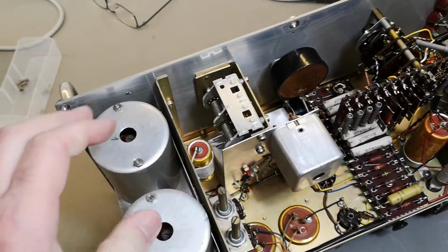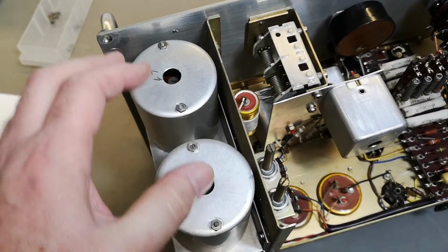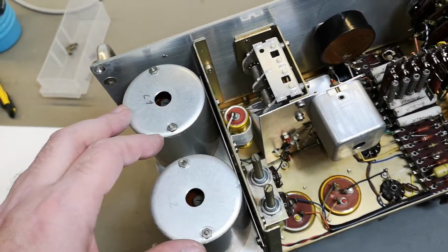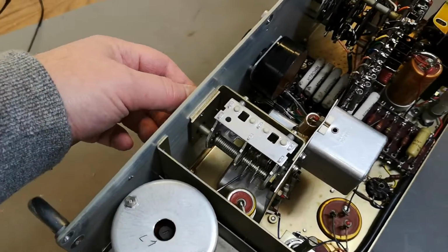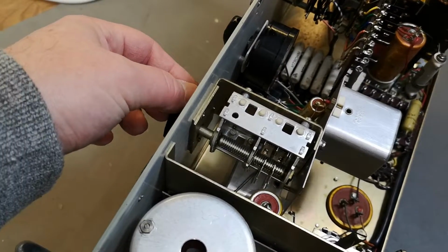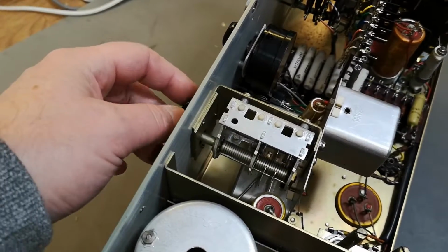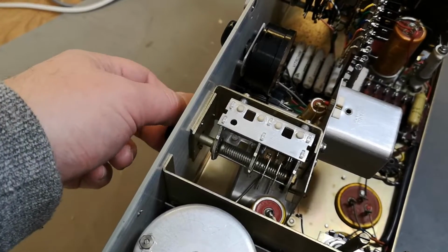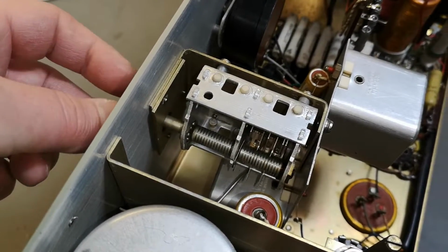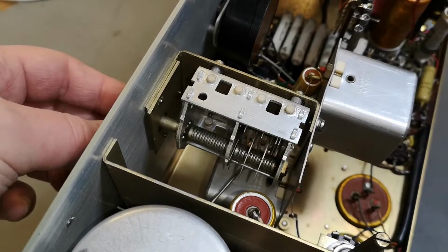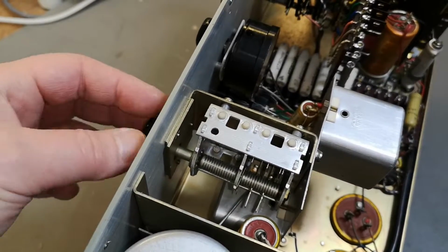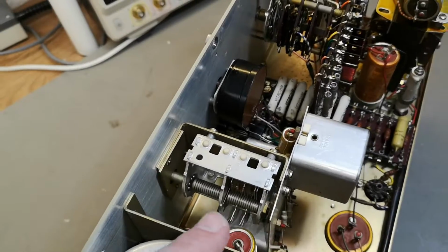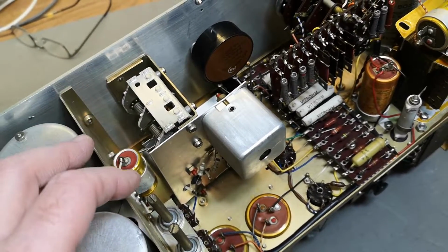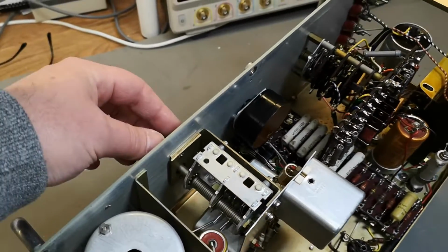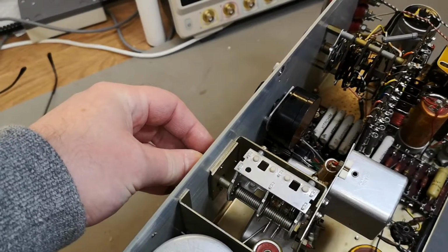That's probably the two inductors used for the two oscillators, and that will be the zero adjustment. Look at that, the capacitor here is just for fine tuning. So I bet we have to set this in center and then perform tuning on all sorts of other methods when we're inside here, otherwise we can't compensate for any drift.